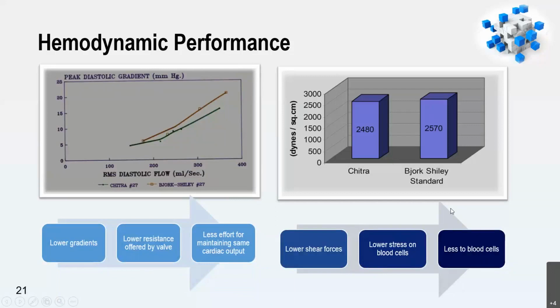Then these are some of the results from those studies. The one on the left side shows the gradient. The gradient is the pressure drop across the valve for different flow rates. And the lower the gradient, the lower the resistance offered by the valve, so less effort is required for maintaining the same cardiac output. So it is matching with the control devices. Similarly, this is another parameter called the shear forces on the blood when the valve is functioning. When you have higher shear forces, it can lead to damage to the blood cells and eventually lead to anemia or platelet adhesion, various complications related to damaged blood cells. So here also what we need is lower levels of shear forces.